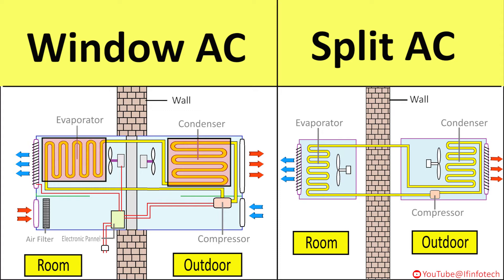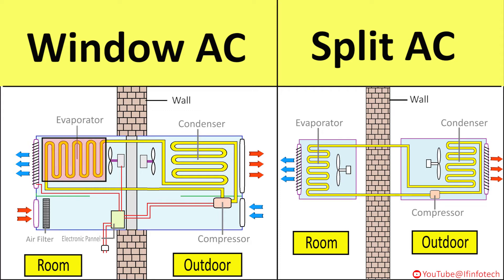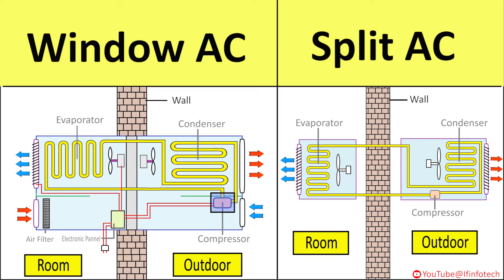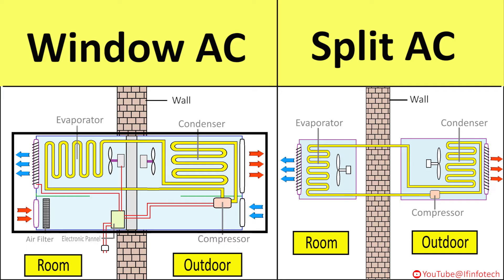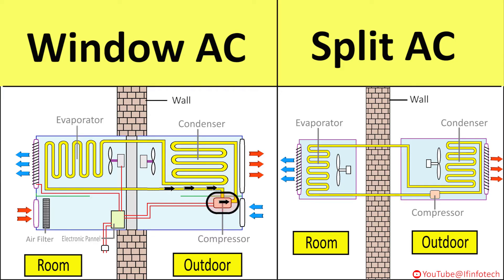The condenser is connected to the evaporator by capillary tube. The evaporator is connected to the compressor by suction pipeline, and the compressor is connected to the condenser by discharge pipeline. In window AC, a simple vapor compression refrigeration system is used. The low pressure, low temperature refrigerant vapor is sucked by the compressor, compressed to high pressure and high temperature, and discharged to the condenser.